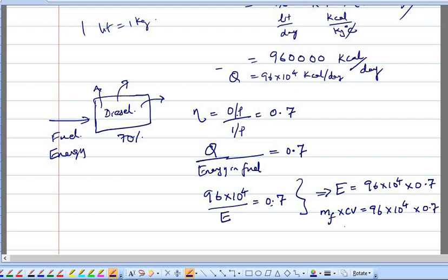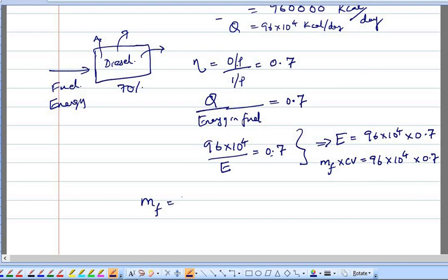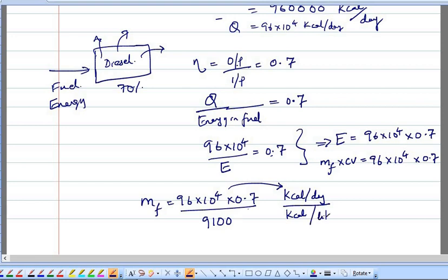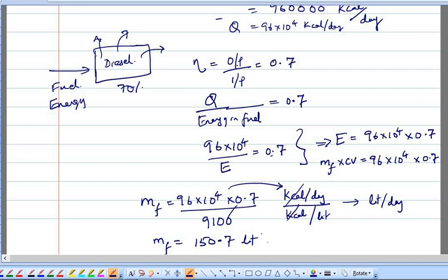The mass of fuel is unknown and the calorific value is 9,100 kilocalories per liter. So mass of fuel = (96 × 10⁴ × 0.7) ÷ 9,100. The units work out as kilocalories per day divided by kilocalories per liter, giving liters per day. Solving this, the mass of fuel consumed is 150.7 liters per day.